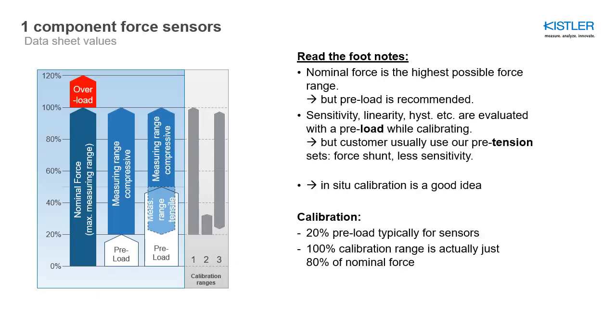Now to sum up everything, let's go back again to an overview. We were talking about the nominal force, which is the maximum measuring range that you can see here on the left. We allow 20% of overload, which you can see here in red on the left side. We were talking about the measuring range of the compressive force, which is the nominal force minus the preload. And we were talking about the measuring range of tensile forces, which depends on the amount of preload that is applied to the sensor. Just a remark on the datasheet as such, it is always a good idea to read the footnotes, because the preload is only recommended and not really visible there on the sheet.